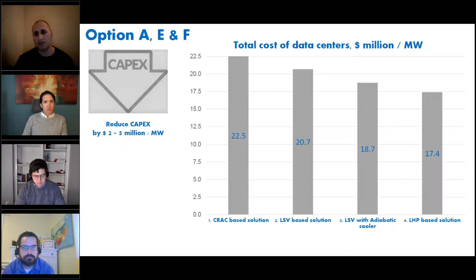And this is the total cost of data centers. If we compare the conventional, CRAC-based solution, the average price of data center building is from 15 to 30 million per megawatt. I take the average, and it's 22.5. And in percentage, if you compare the LSV-based solution and LSV with adiabatic coolers and LHP, it goes down. That's the trend which I want to show, that the data center will be more efficient and lower in price, and that's the market demand.